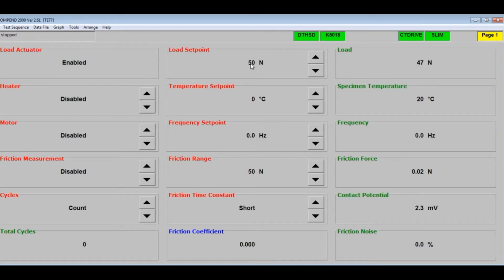To set the charge amplifier for friction force measurement, use the up and down arrows to scroll between short, medium and long time constant. Short and medium are used for dynamic force measurement, and long is used for quasi-static force measurement. Short is used for tests above 2 Hz reciprocating frequency, medium for tests between 0.5 and 2 Hz, and long for low reciprocating velocity tests using the optional reduction gearboxes. The long time constant is also used for calibration.